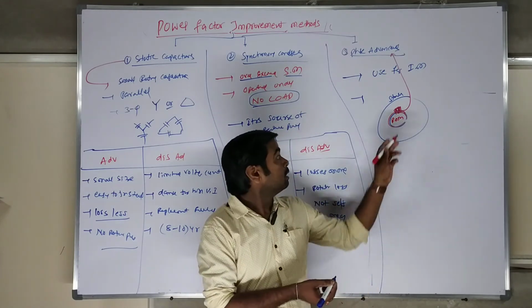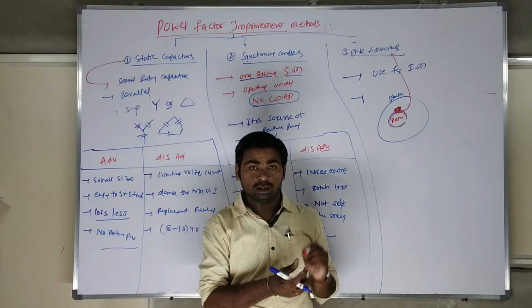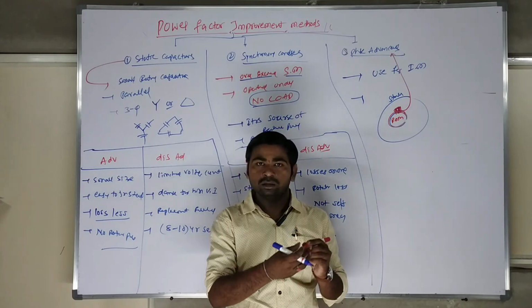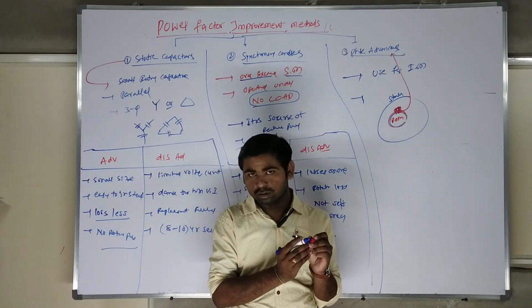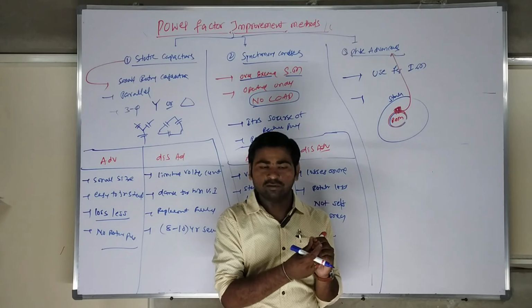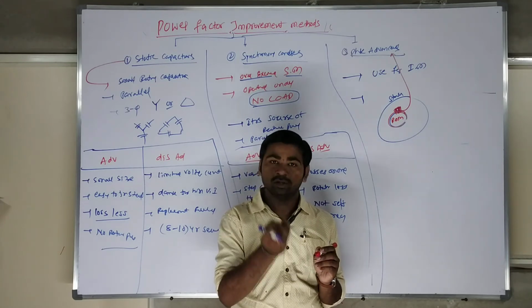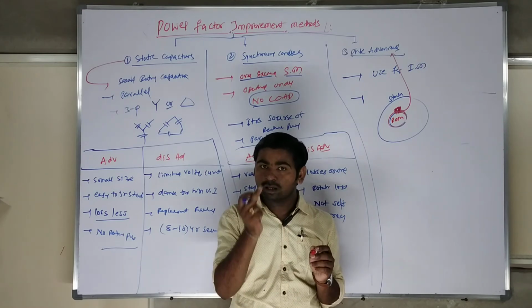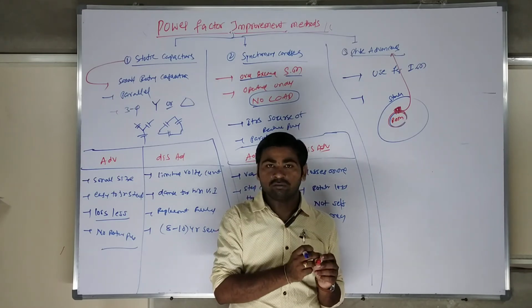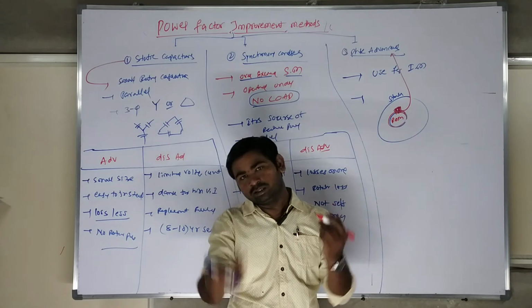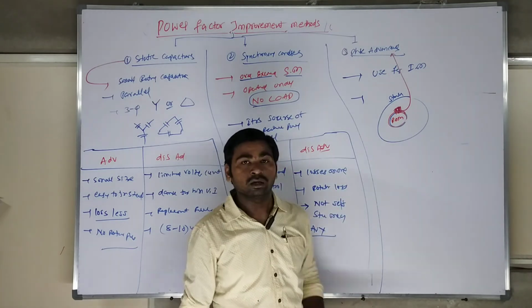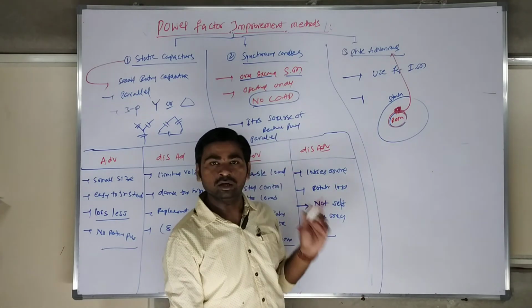The phase advancer on the rotor shaft of the induction motor acts like a generator. When the rotor shaft rotates, the phase advancer rotates, so mechanical energy is converted to electrical energy. That electrical energy is given to the rotor winding, and the rotor winding gets overexcited. Automatically, you can control the reactive power of your induction motor.